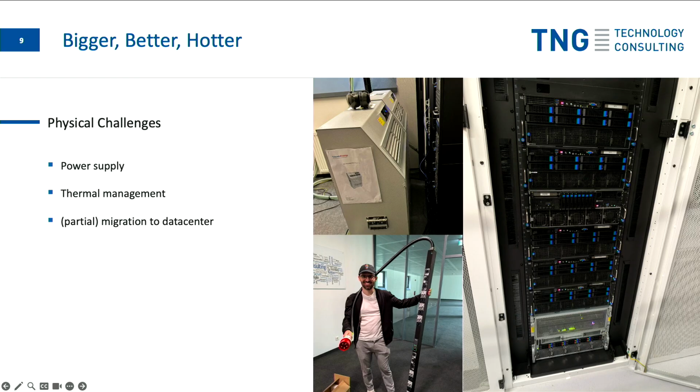So you need some kind of power distribution unit. And then you're happy because you just found a very big power distribution unit, only to find out that it's the wrong type and it is not compatible with the actual hardware that you bought. So those are real challenges. And second challenge, temperature management. 1 kilowatt input power means 1 kilowatt output power. Everything goes into heat. We basically built a very expensive heating system for our server room.